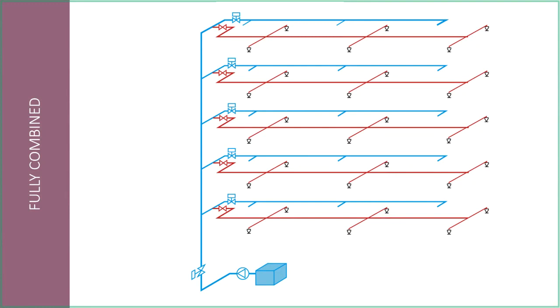So just to run over that again, because that might have been a bit quick. When the sprinkler heads operate, the water comes out of the head, let's say on floor 2. The flow switch on floor 2 will activate and say that there's an activation, there's a fire, and at that point various panels and boxes will talk to each other, and the priority demand valves on all the floors will shut off, which will mean that nobody can open the tap, flush the toilet, put the washing machine on, dishwasher, etc., because all of the water is now solely being used for the sprinklers, which is good because it just means that water is guaranteed for sprinkler use.